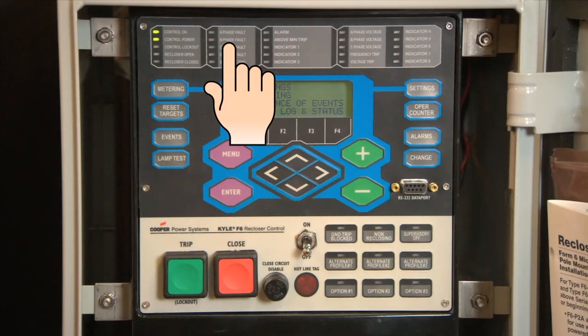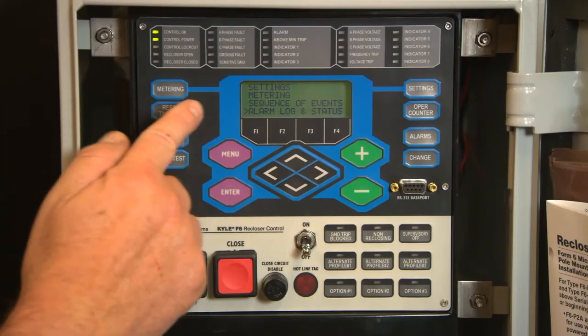Fault location. The control includes an impedance-based fault locator based upon the Takagi algorithm. Load-compensated impedance calculation is used for calculating the distance. Positive and zero sequence is configured in ohms, and the fault locator line length is configured in kilometers/miles. This is the Cooper Form 6 control.